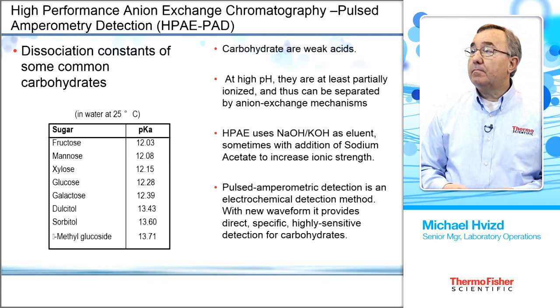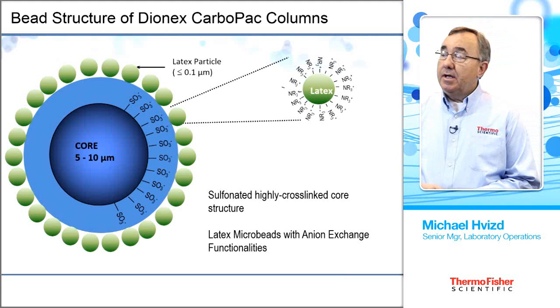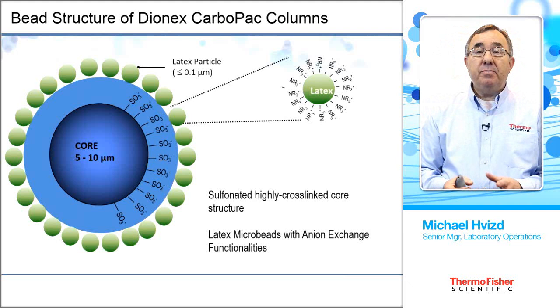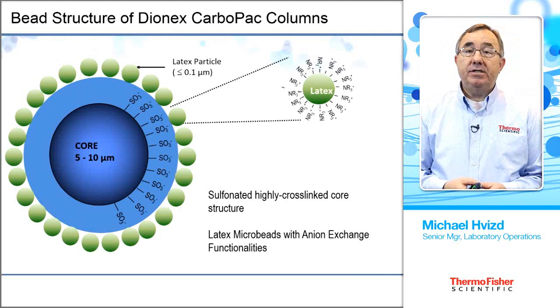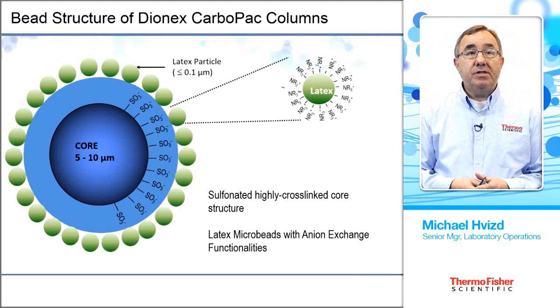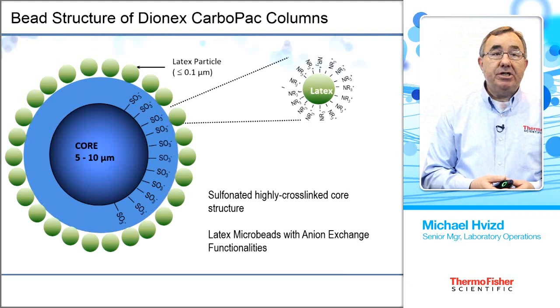Here's an illustration of the column technology developed at Dionex. That column technology has stayed the same over many years. It's basically a polystyrene divinylbenzene core. We surface sulfonate that resin bead, and then attach our ion exchange sites — quaternary amine sites — which are part of the latex particle on the outside of the bead. These latex microbeads are the anion exchange functionalities that do all the work.